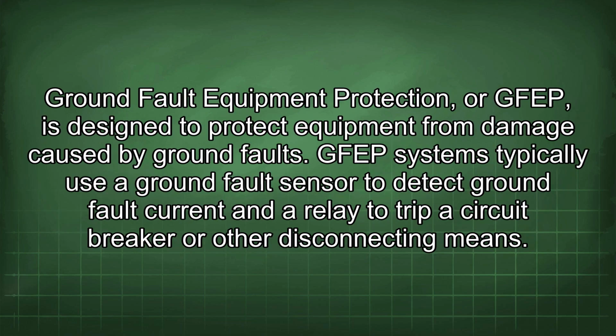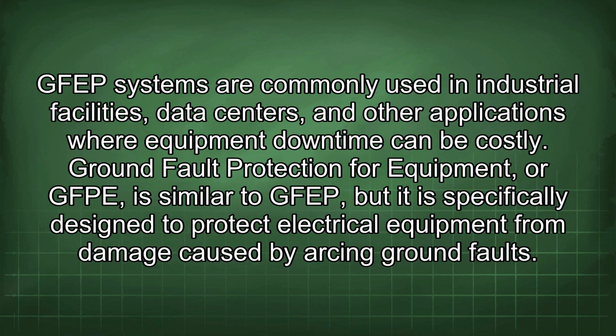Ground fault equipment protection, or GFEP, is designed to protect equipment from damage caused by ground faults. GFEP systems typically use a ground fault sensor to detect ground fault current and a relay to trip a circuit breaker or other disconnecting means. GFEP systems are commonly used in industrial facilities, data centers, and other applications where equipment downtime can be costly.